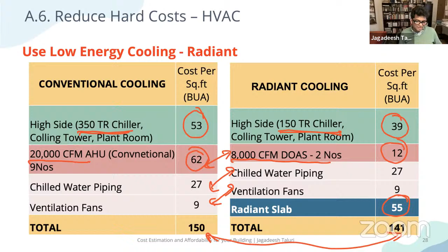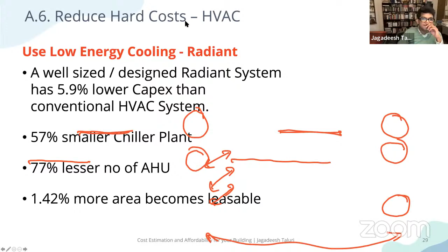That is because of right sizing. In right sizing, you're not only replacing a low efficiency system with a high efficiency system, but you're also reducing the size of the high efficiency system. So basically, this is what happens. A well-designed radiant system has 5.9% lower capex than any conventional HVAC system. This is true whether it's a residential building or an office building. In both scenarios, radiant works quite well, and your chiller plant size can reduce even up to 57%.